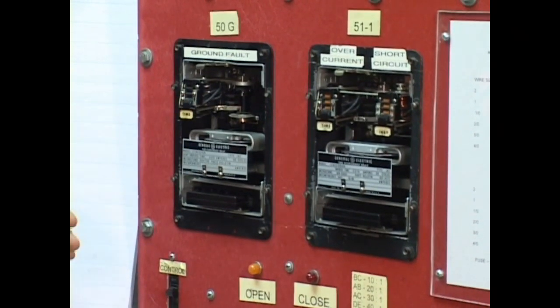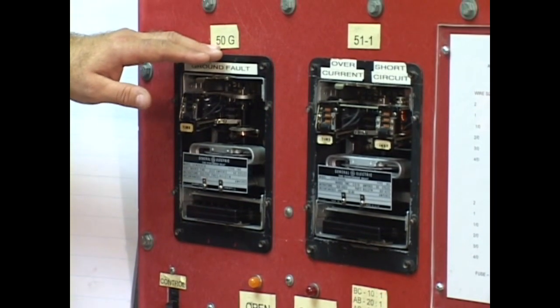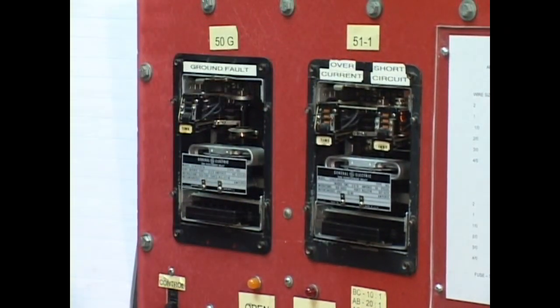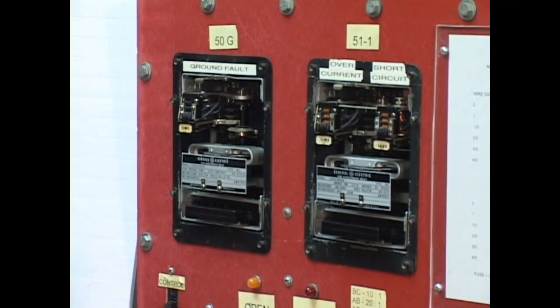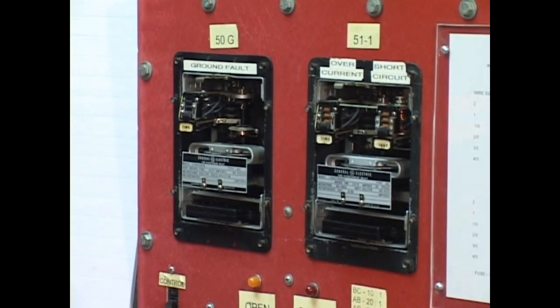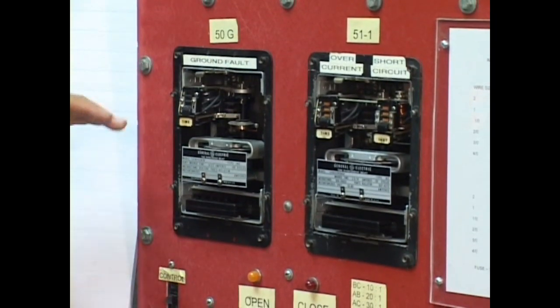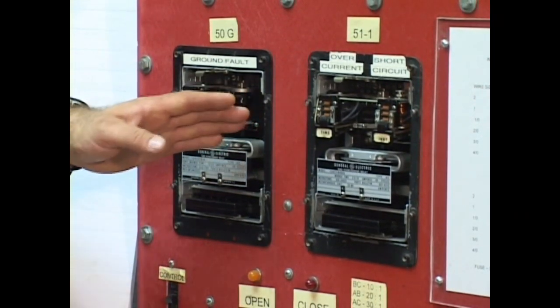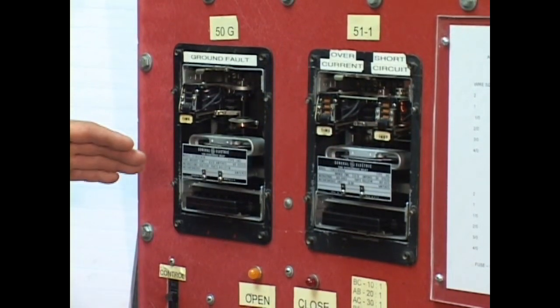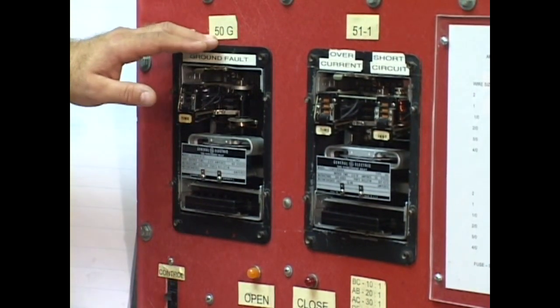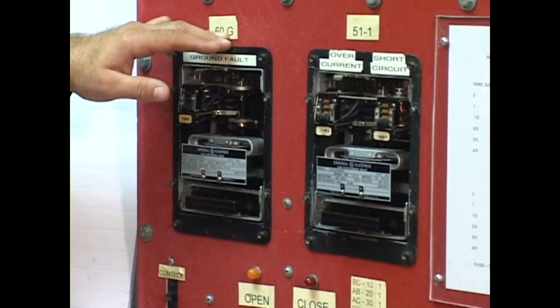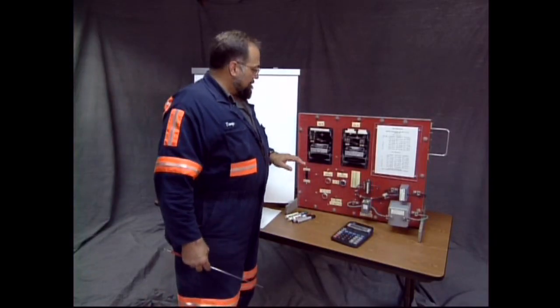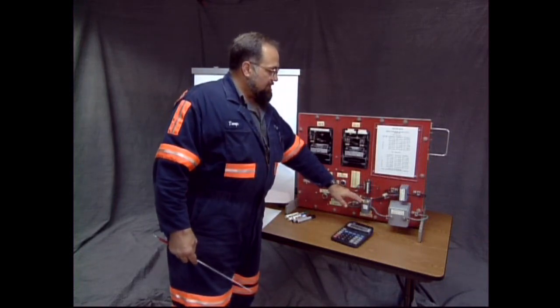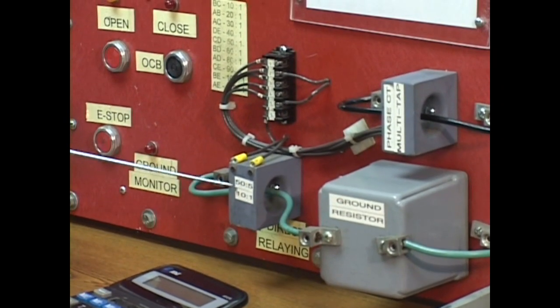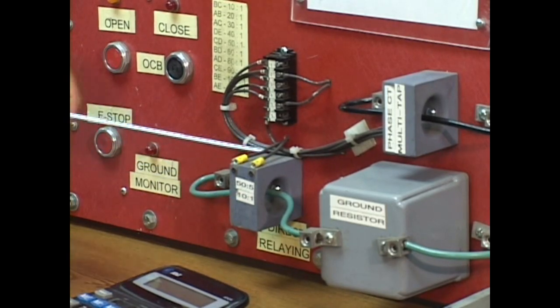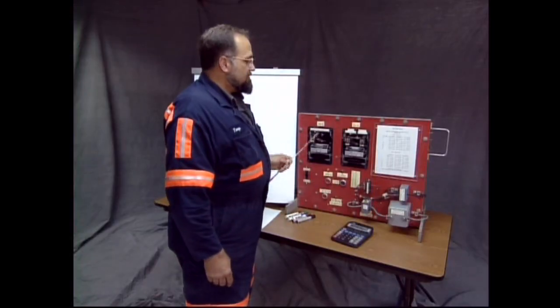You have two relays. Note one of them is labeled 50G. The other one's labeled 51-1. Well, they're both time over current relays. Technically, they're both a time over current relay. A device 50, as you can see, doesn't have an instantaneous unit. It has only a time unit. Device 50 is for the ground, hence the G. It's supplied by the CT on the ground wire, this one here. The CT with the green wire passing through it from the ground resistor, that's the ground, supplies this device.